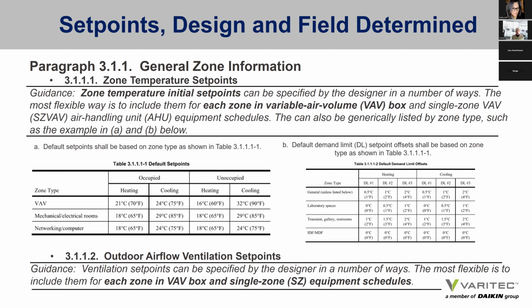The most flexible way is to include them in each zone in variable air volume box schedules or in air handler schedules. I know at Varitec, I've actually written VAV schedules that include the values proposed by Guideline 36 to more easily facilitate the incorporation of those schedules into an engineer's specification. There's also outdoor airflow ventilation rate set points provided by the guideline, and it gives ventilation set points that can be specified by the designer in a number of ways.